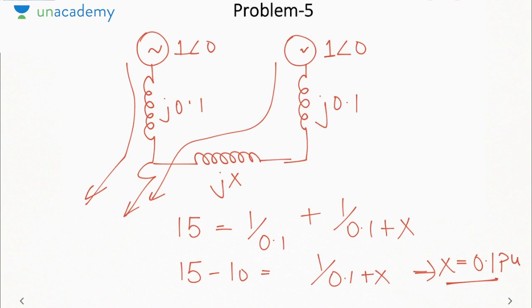That will be the current limiting reactor X to be installed to limit the short circuit fault current to 15 pu. Okay, so that is how we design the rating and the value of the current limiting reactor for the case of power system protection, or based on the fault analysis.